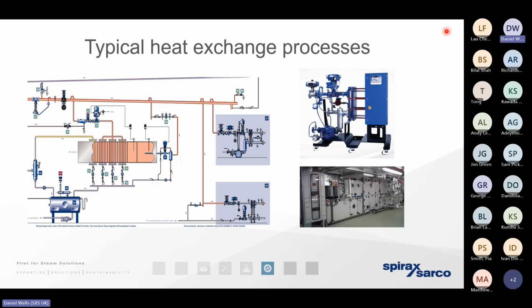And we can be using the steam in different ways. There are 2 different ways. It's what we call direct usage. That's generally when the steam is going to come into contact with the product or the atmosphere. So it could be humidification in a hospital operating theatre or in a pharmaceutical clean room. It could be for sterilizing a jam jar, or it could be for injecting steam directly into a vat of orange juice or milk. That's what we call a direct process.